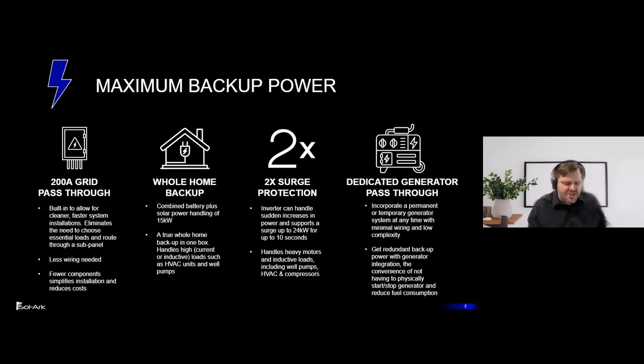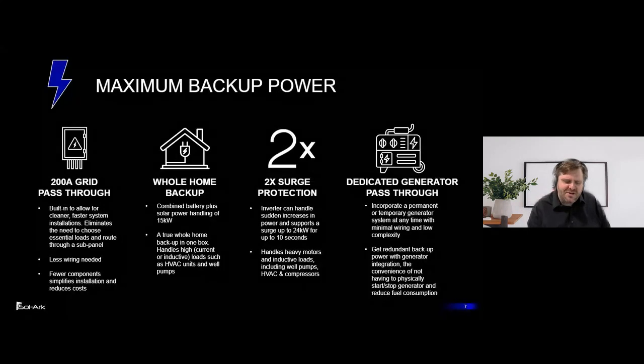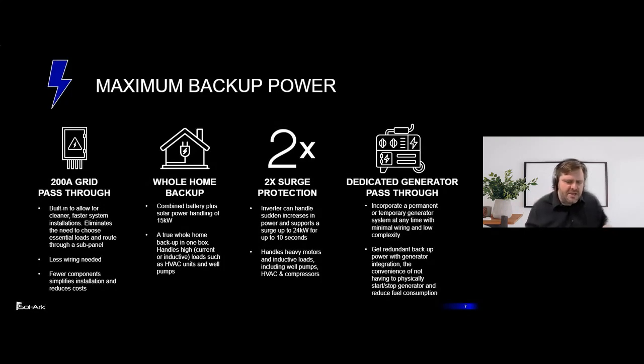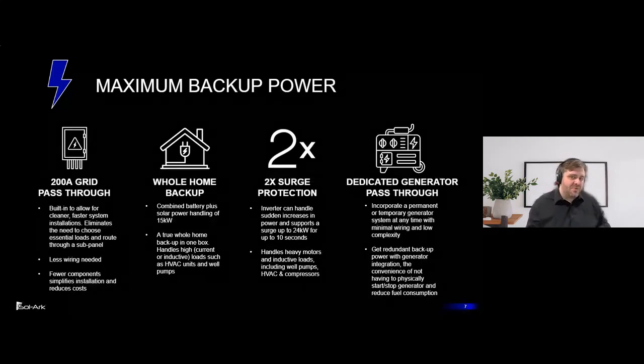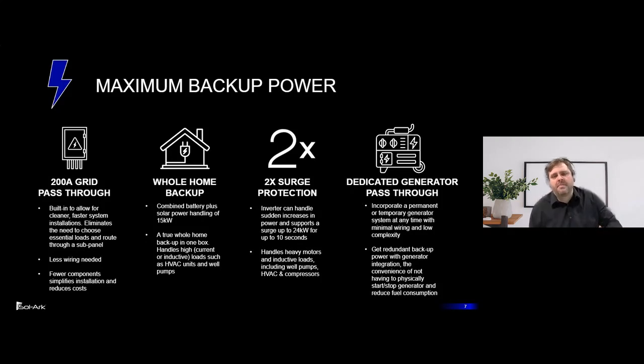Budget is a consideration. Customers don't want to spend too little and not have enough, but in most cases, you are budget constrained and you need to get the most bang for your buck. And the fact is, you look at Sol-Ark's 15K inverter and you go look at whole home backup generators, and they're in the 20 kilowatt, 22 kilowatt range. So if you go smaller than a Sol-Ark 15K, you're really off the mark when it comes to whole home backup.